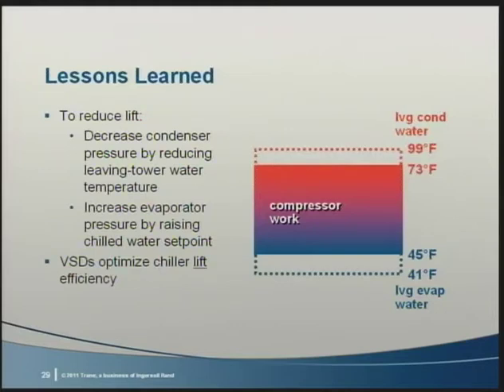There is a relatively small impact on lift when load is reduced because the delta T through the condenser is lower at part load. In many cases, chilled water temperature is constant. Therefore, reducing condenser water temperature is used to reduce lift. Understanding the differences between load and lift is critical to ensure the benefits of drive technology are attainable and balance the higher first cost with potential energy savings.